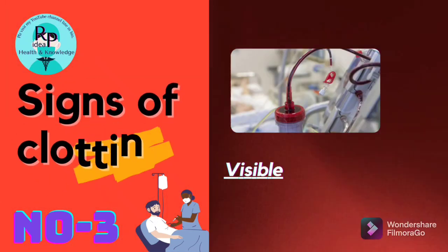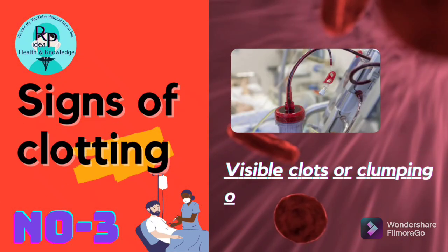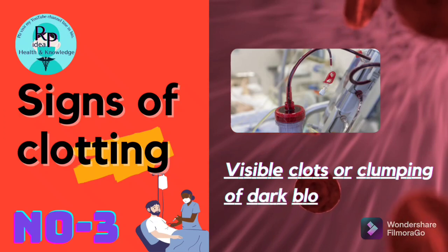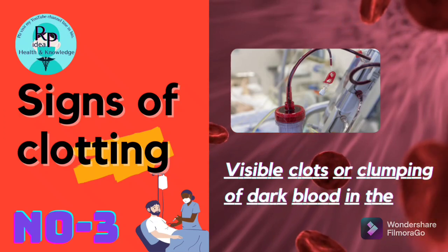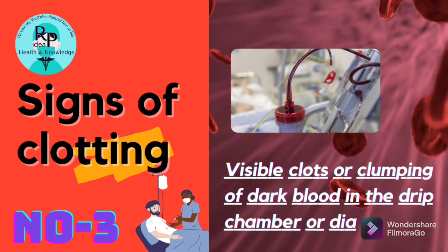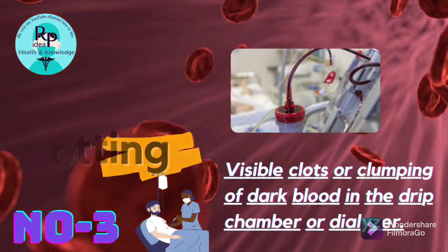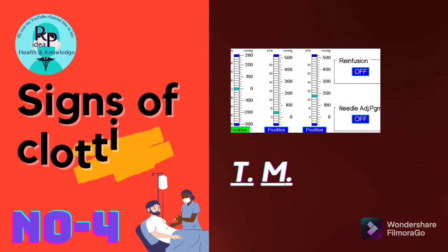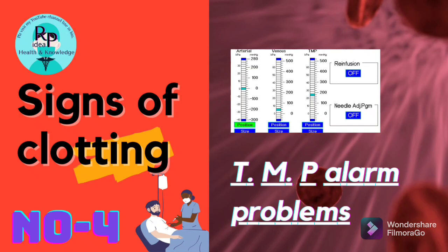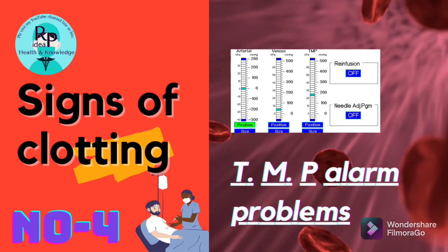3. Visible clots or clumping of dark blood in the drip chamber or dialyser. 4. TMP alarm problems.